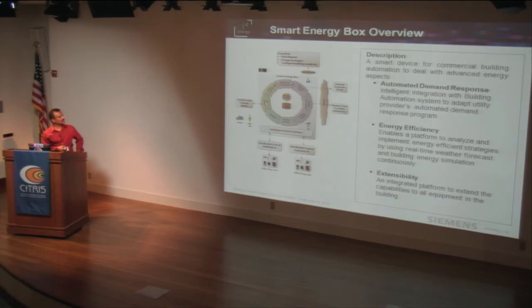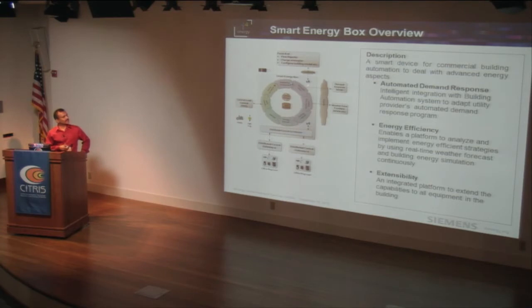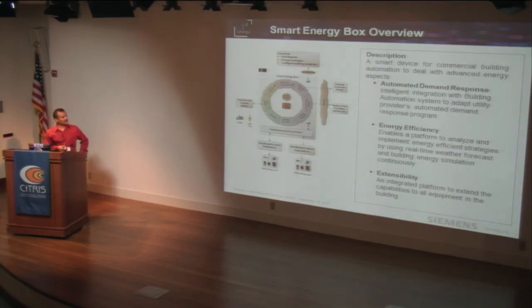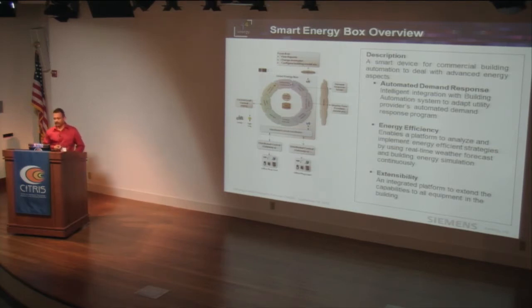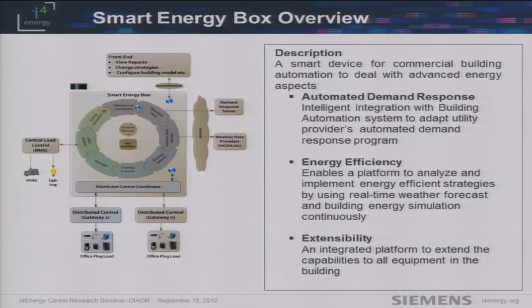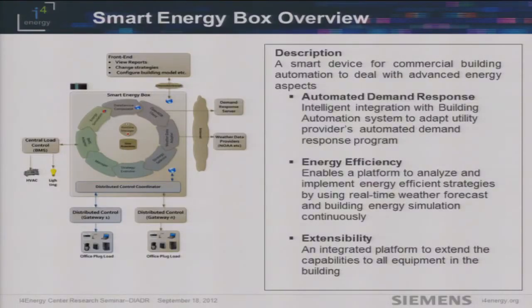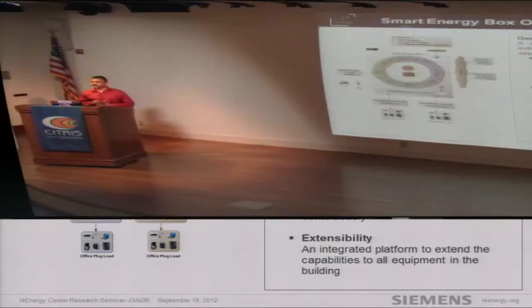We have an OpenADR client which brings the DRAS signal — demand response event information — into the box, talking to the utility provider DRAS. We also bring in real-time weather forecast from the NOAA Weather Service. We configure building energy strategies into the box; it evaluates all of them and makes them available for execution. It also communicates with the building management system to adapt the energy strategies.